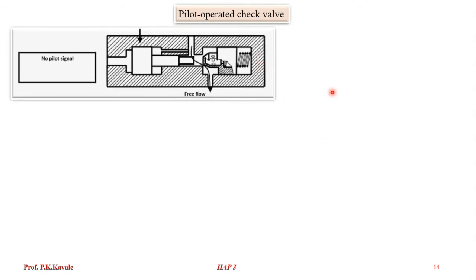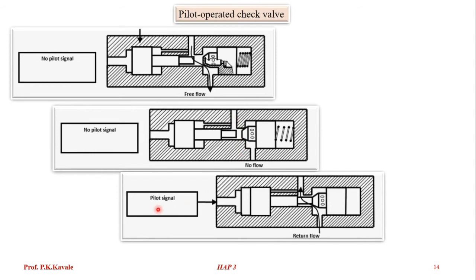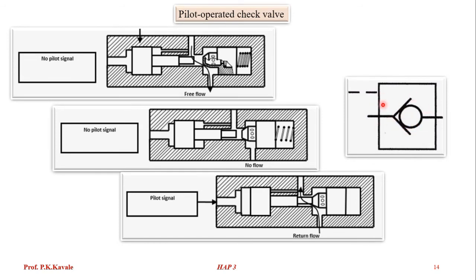The pilot-operated check valve: when there is no pilot signal, it acts as a normal check valve — allowing flow in only one direction (top to bottom). Reverse flow (bottom to top) is not allowed. But in special situations, when a pilot signal is given from a third-party source, the spool moves and opens the valve, making flow in the reverse direction possible. The symbol shows a normal check valve plus a pilot line.